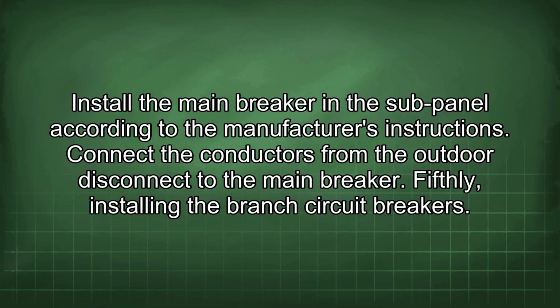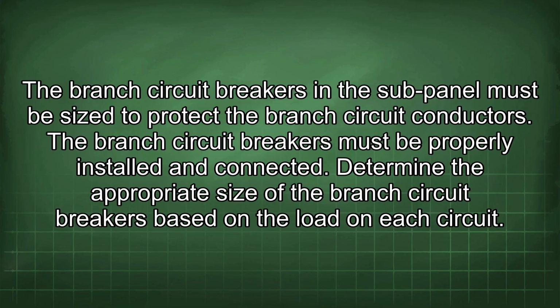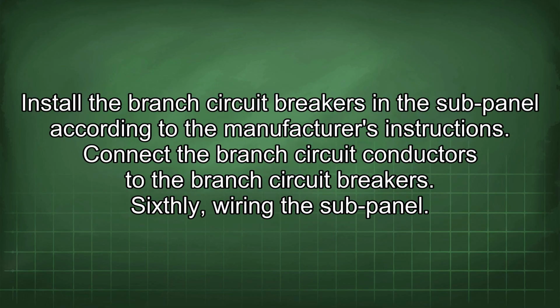Fifthly, installing the branch circuit breakers. The branch circuit breakers in the sub-panel must be sized to protect the branch circuit conductors. The branch circuit breakers must be properly installed and connected. Determine the appropriate size of the branch circuit breakers based on the load on each circuit. Install the branch circuit breakers in the sub-panel according to the manufacturer's instructions. Connect the branch circuit conductors to the branch circuit breakers.